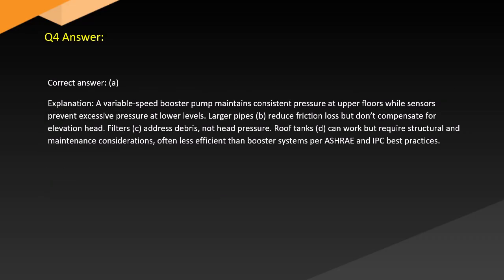Answer. Correct answer: A. Explanation. A variable speed booster pump maintains consistent pressure at upper floors while sensors prevent excessive pressure at lower levels. Larger pipes (B) reduce friction loss but don't compensate for elevation. Inline filters (C) address debris, not head pressure. Roof tanks (D) can work but require structural and maintenance considerations, often less efficient than booster systems per ASHRAE and IPC best practices.